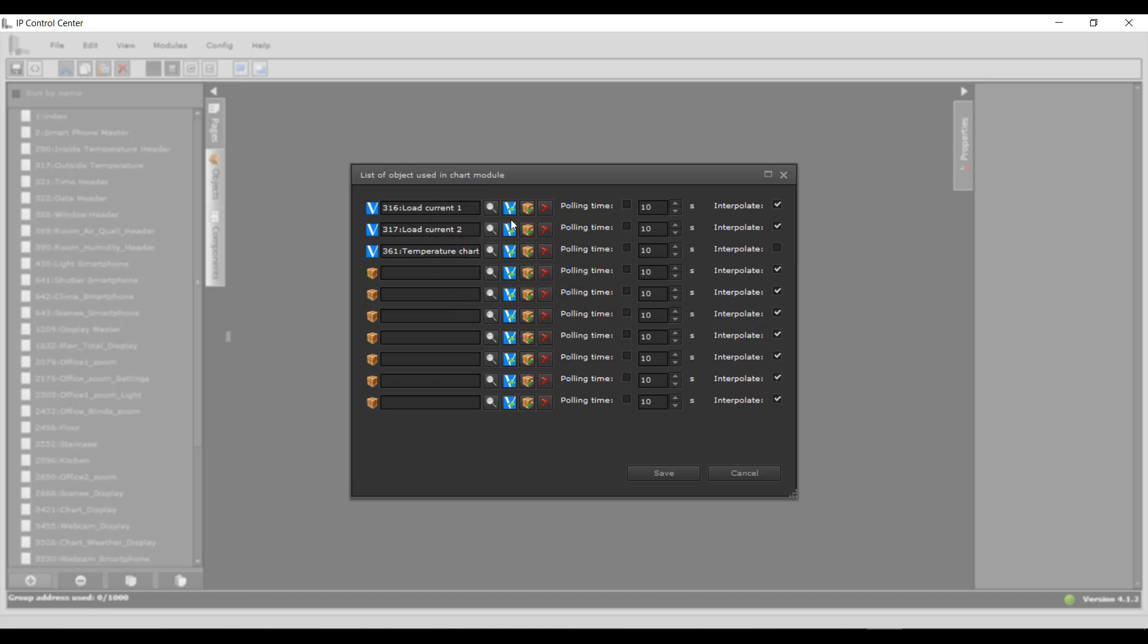The following settings are possible on this page. Polling Time: When this setting is activated, the respective data point is queried cyclically. A read request is sent to the KNX bus in the process. The polling interval is also defined in seconds.